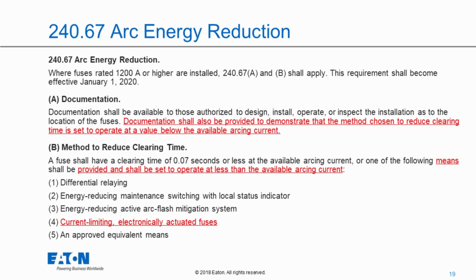So we have to document that whatever we do, we either have to show that the fuse has a clearing time of 0.07 seconds, or we have to show that the options, differential relaying, energy reducing maintenance switching with local status indicator, energy reducing active arc flash mitigation system, or now in the 2020 NEC, current limiting electronically actuated fuses, if the fuse can't do it, that the different technologies in items 1 through 4, or perhaps new technology that would be permitted per list item 5, will operate again within the arcing current.